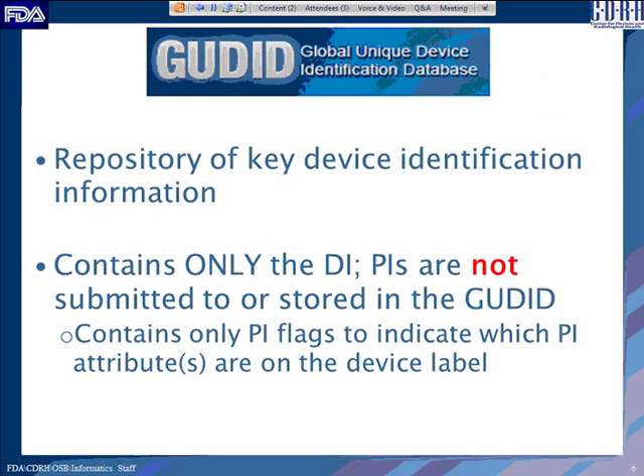GUDID — the Global Unique Device Identification Database — is a repository of device identification information. GUDID will only contain the DI, the static portion that is not changing for a given version or model. Production identifiers are not submitted to or stored in GUDID. Instead, GUDID asks you to indicate which production identifiers are on the label — for example, whether the lot number is on the label: yes or no. That is the only information collected about a production identifier in GUDID.